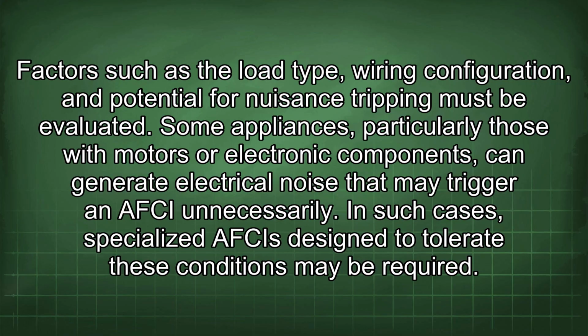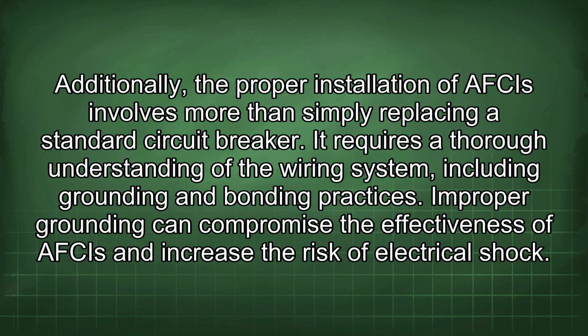Some appliances, particularly those with motors or electronic components, can generate electrical noise that may trigger an AFCI unnecessarily. In such cases, specialized AFCIs designed to tolerate these conditions may be required. Additionally, the proper installation of AFCIs involves more than simply replacing a standard circuit breaker. It requires a thorough understanding of the wiring system, including grounding and bonding practices.